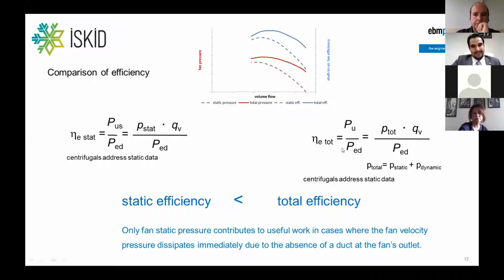This is also explained with that formula. The total pressure is the static plus the dynamic, the flow pressure. And only the fan static pressure contributes to the job, which is to overcome the losses, the resistances in an air handling unit, the internal losses or the external losses created by the duct system, bends, and all these parts. So if you compare fan effectiveness, you have to bring the data to the same level. In some documentation, you see the total efficiency; in some documentation, you see the static efficiency. That's the point here, to make the data comparable.